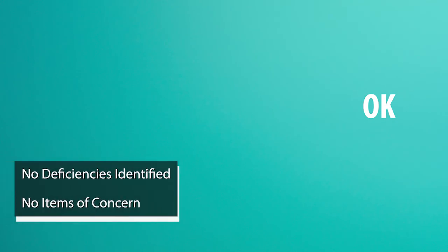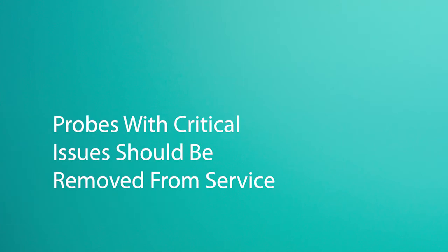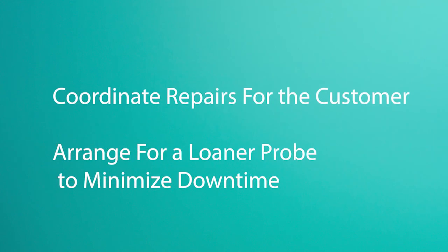OK indicates no trouble was found and the probe meets all safety and functional expectations. Any probes with findings deemed a patient safety issue should be addressed with an extremely high priority, and probes requiring service for minor cosmetic issues or minor issues can be of a lower priority.